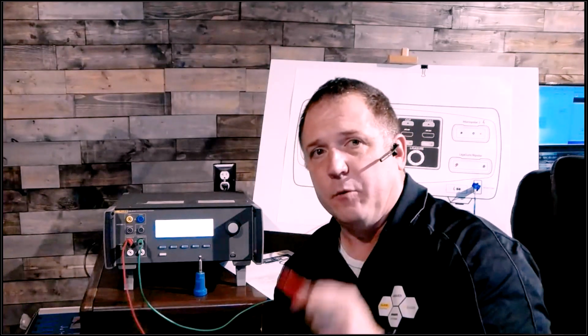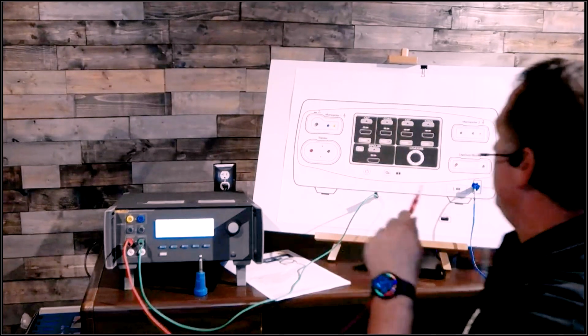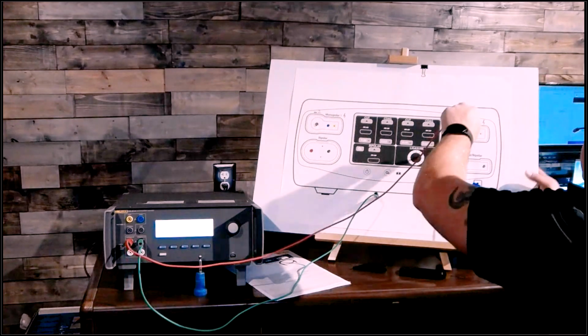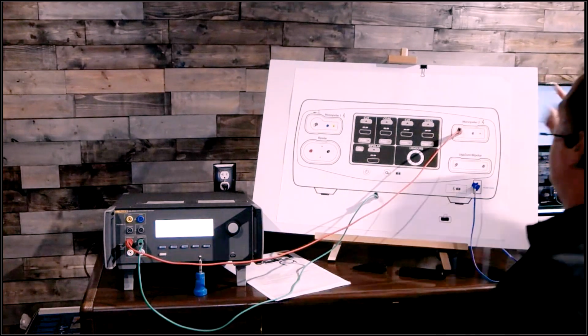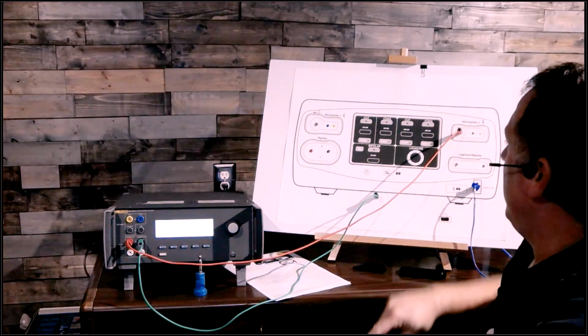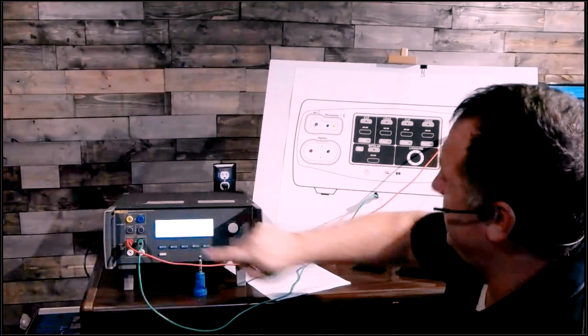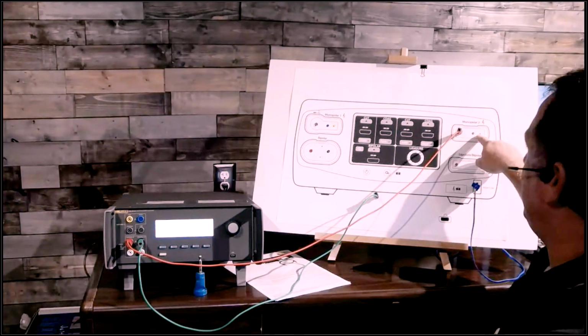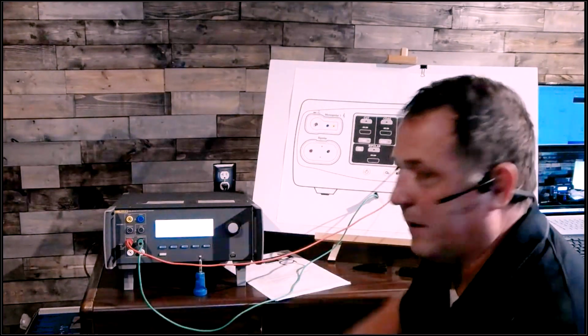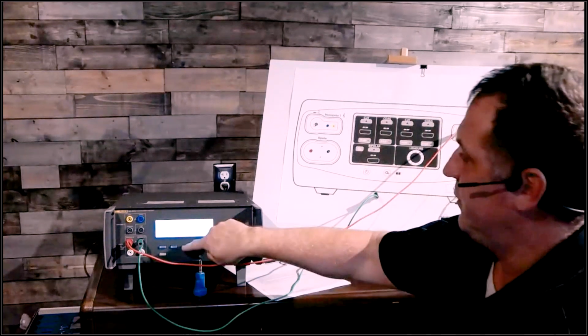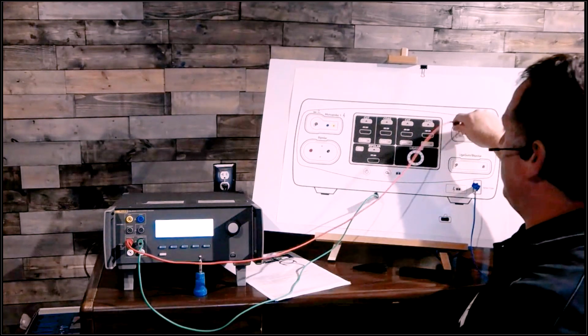It'll tell you which one to do first, but normally monopolar cut here. I'd run this up to max wattage, start continuous here, activate my ESU, and I want to have less than 150 milliamps. Stop here, and then test monopolar 1.